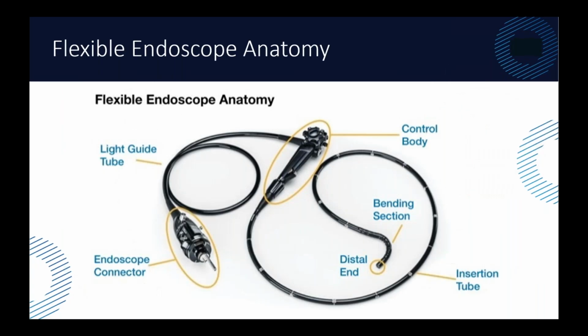So let's talk about anatomy. In this case, we're going to look at flexible endoscope anatomy. And I think we'll go ahead and start here at the distal end, the distal tip. In the endoscope, most of the time these days, we're talking about some sort of camera that's going to be there. On the TE probe, it's going to be an ultrasound element. And in some endoscopes, it's going to be both camera and ultrasound at the same time. So a lot going on in that tip. The tip is pretty much, give or take, about the size of one of my fingers, very small, very tiny. And everything is meant to support that.